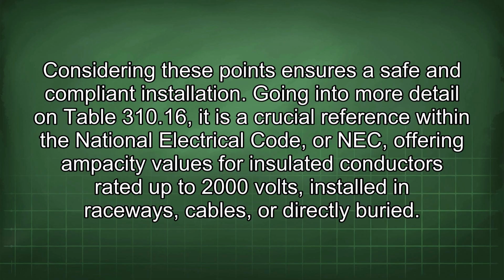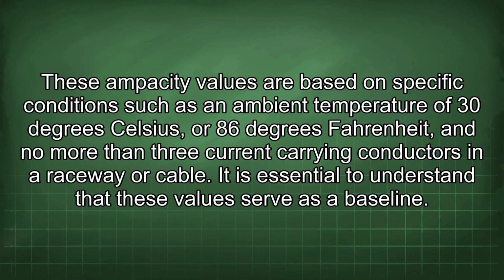Going into more detail on Table 310.16, it is a crucial reference within the National Electrical Code, or NEC, offering ampacity values for insulated conductors rated up to 2000 volts, installed in raceways, cables, or directly buried. These ampacity values are based on specific conditions such as an ambient temperature of 30 degrees Celsius, or 86 degrees Fahrenheit, and no more than 3 current carrying conductors in a raceway or cable.